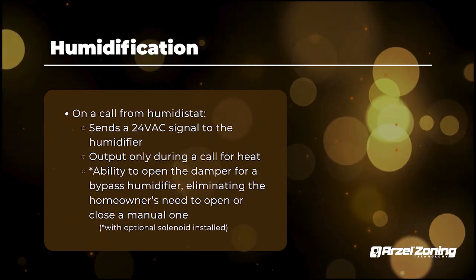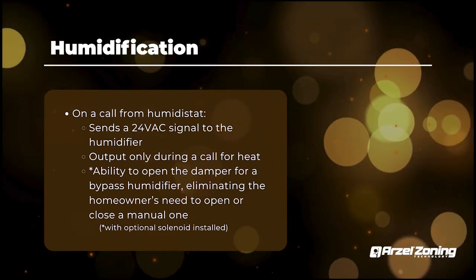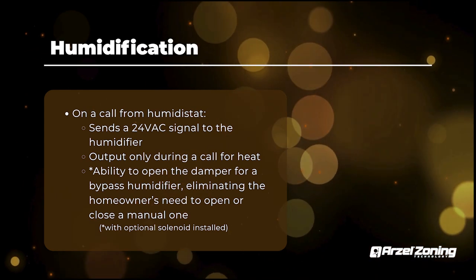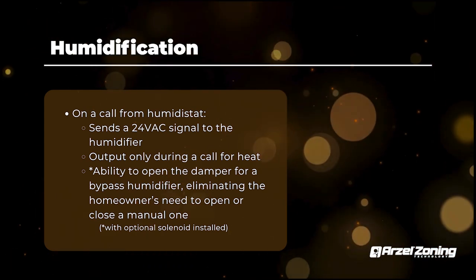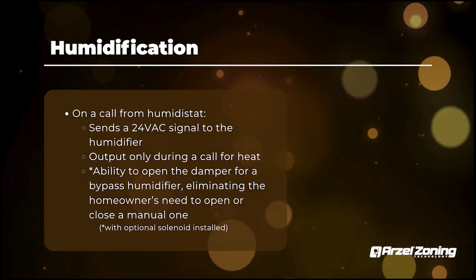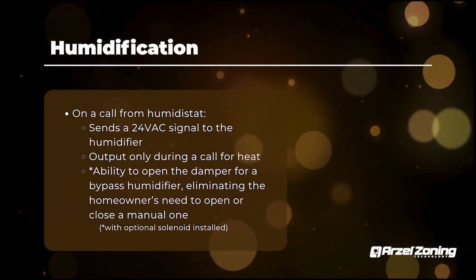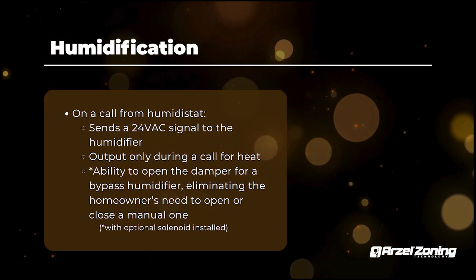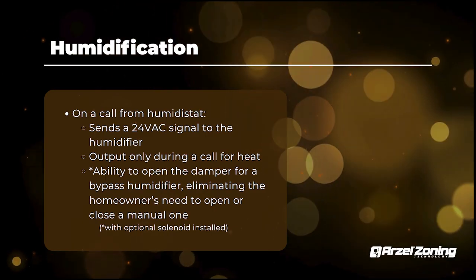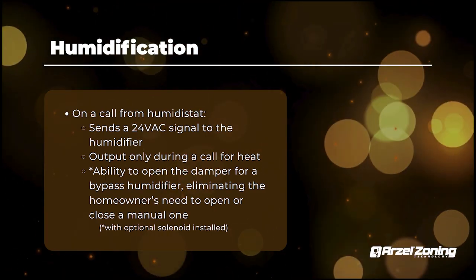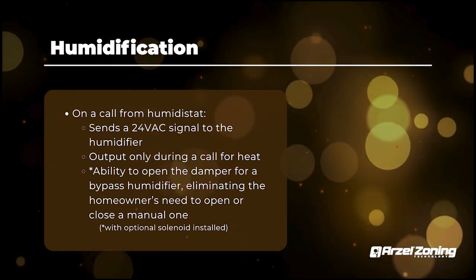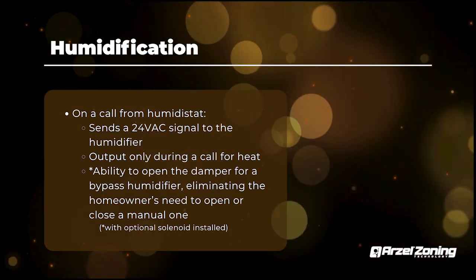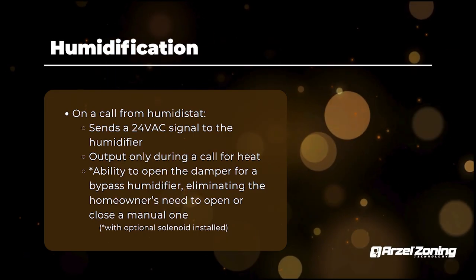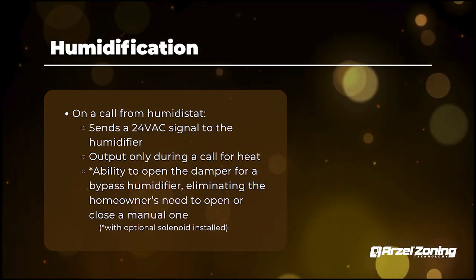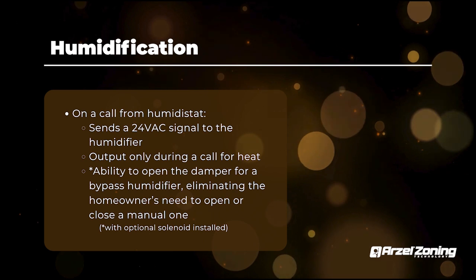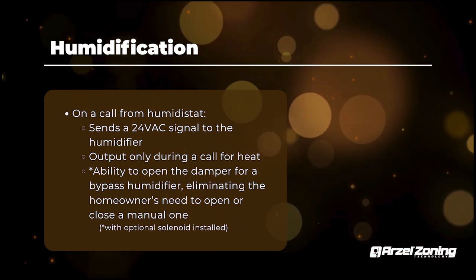As far as humidification goes, it does give you a humidification terminal on your zone 1. So you guys can do a thermostat that controls humidity, or you can do a humidistat if you want. Up to you guys. With the HeatPumPro though, something to keep in mind if you're going to use the humidification terminal, it only energizes with a heating call. So if you're trying to do blower activation, this terminal is not going to work for what you want it to do. If you guys want to do blower activation, ignore the Arzel panel completely, wire it independent of the zoning panel, so straight to your HVAC equipment, and let your equipment actually kick on with the blower.